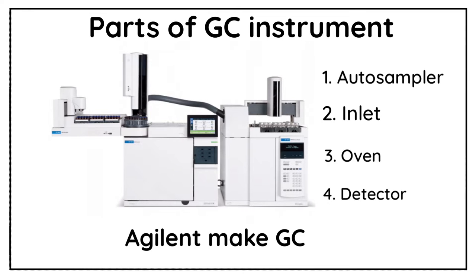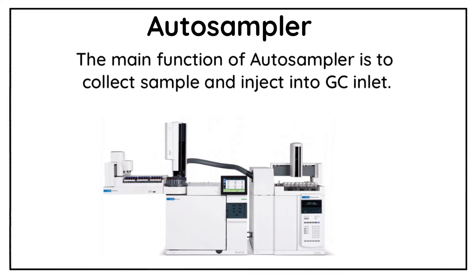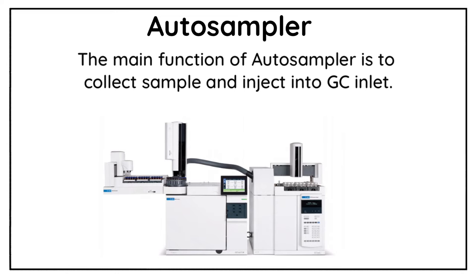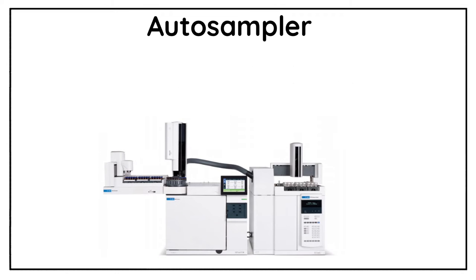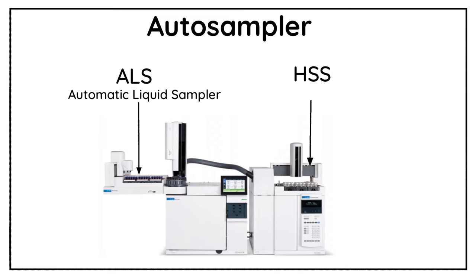Now let us know a little bit more about these parts. Firstly we will talk about the auto sampler. The main function of the auto sampler is to collect the sample from the sample vial and inject it into the GC inlet. Generally a GC instrument comes with two types of auto samplers: ALS and HSS. ALS means Automatic Liquid Sampler and HSS means Headspace Sampler.